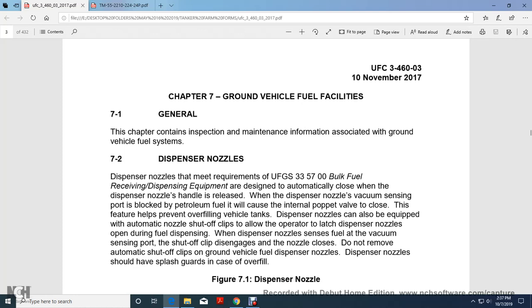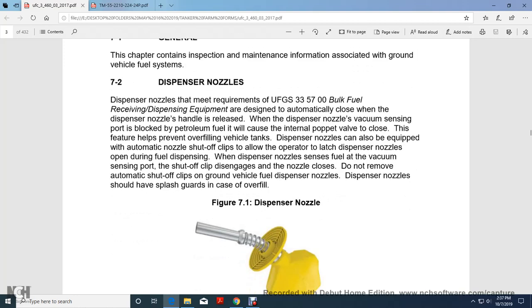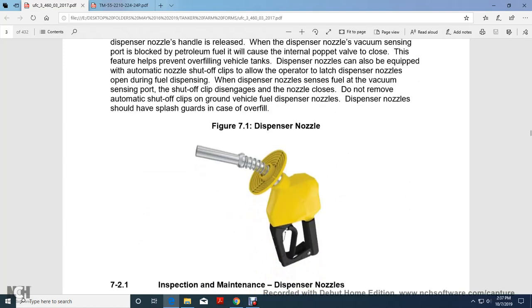The dispenser nozzle can also be equipped with automatic nozzle shut-off clips that allow the operator to latch the dispenser nozzle open during fueling. When the dispenser nozzle senses fuel at the vacuum sensing port, it shuts off and the clip disengages the nozzle latch. Do not remove the automatic shut-off clips of the ground vehicle fuel dispenser nozzles. Dispenser nozzles should have splash guards in case of overfill.